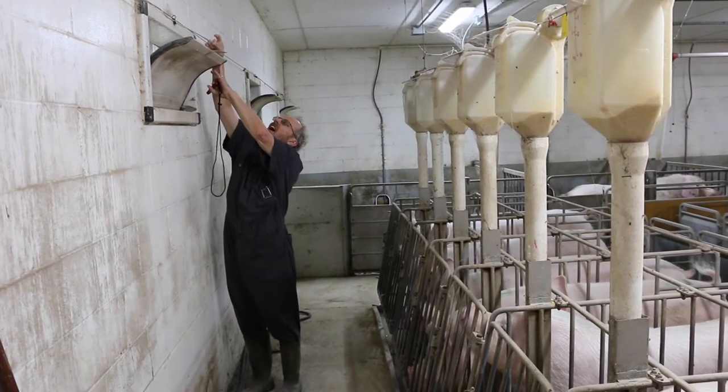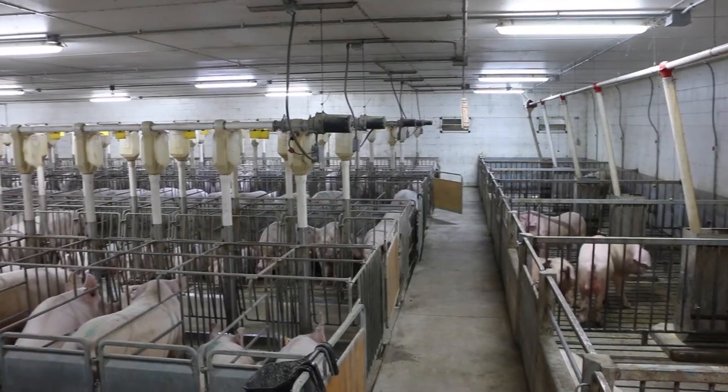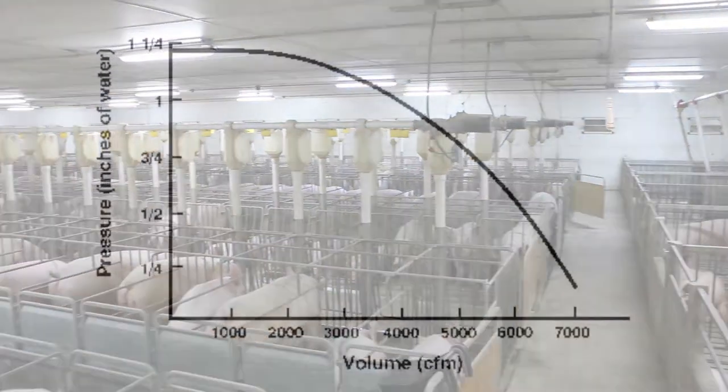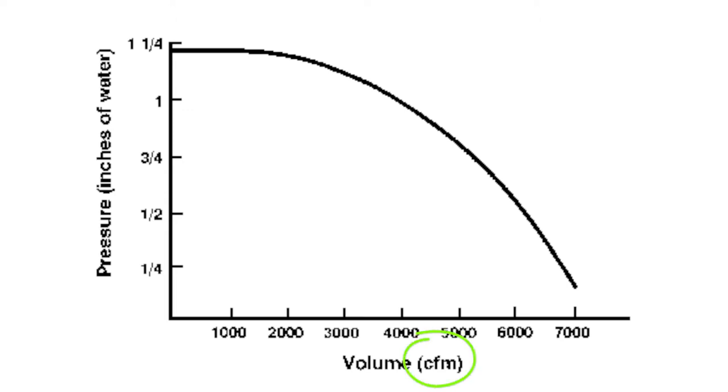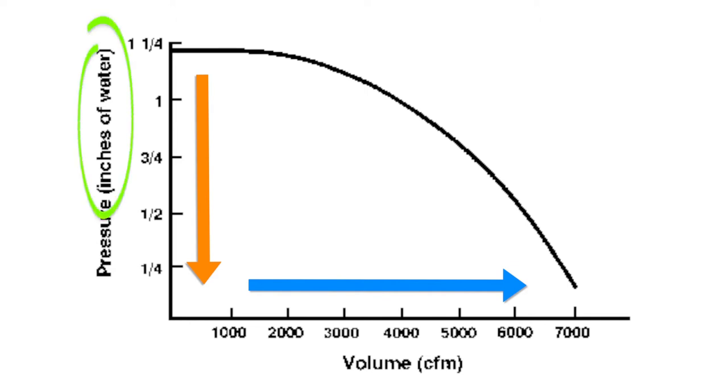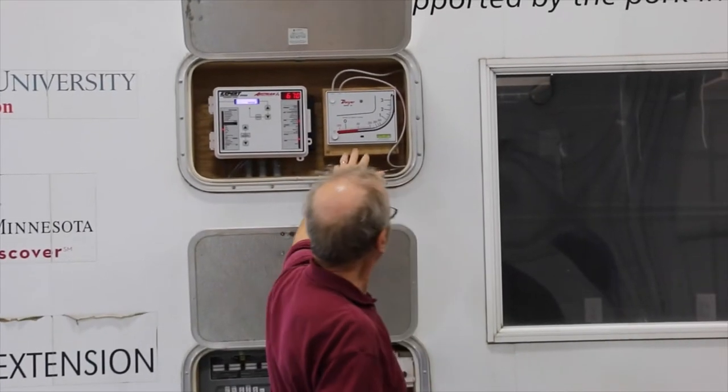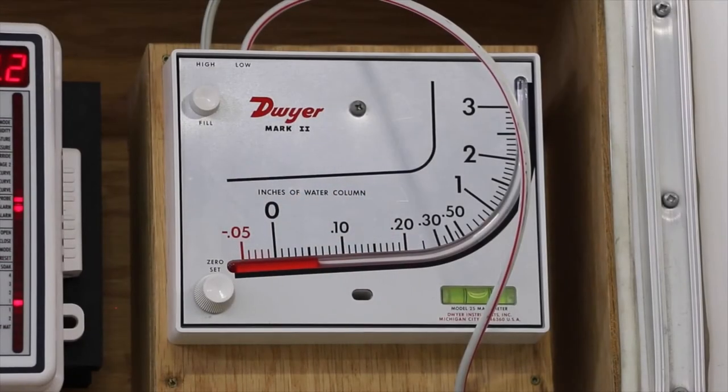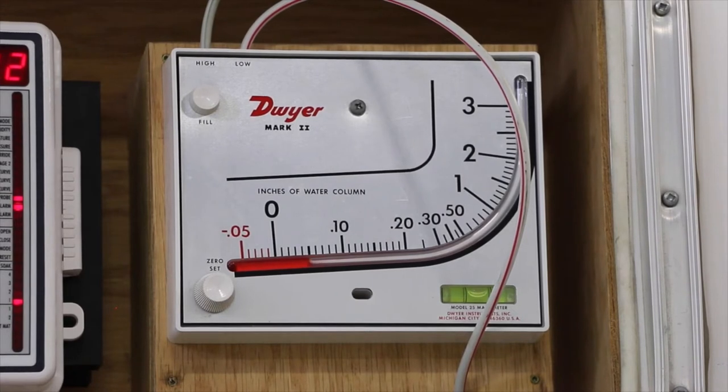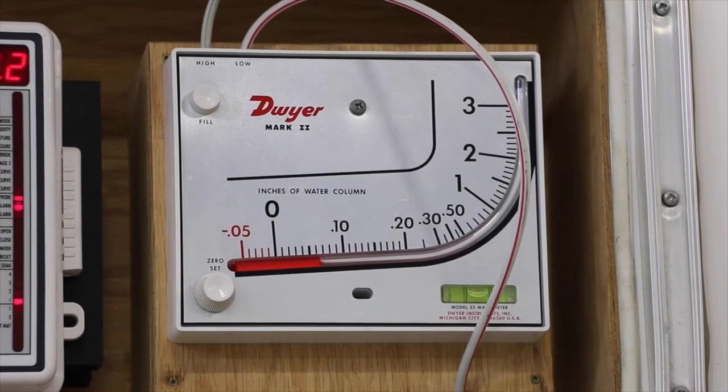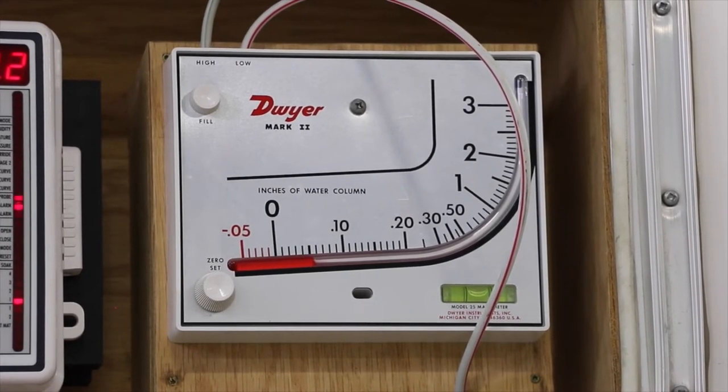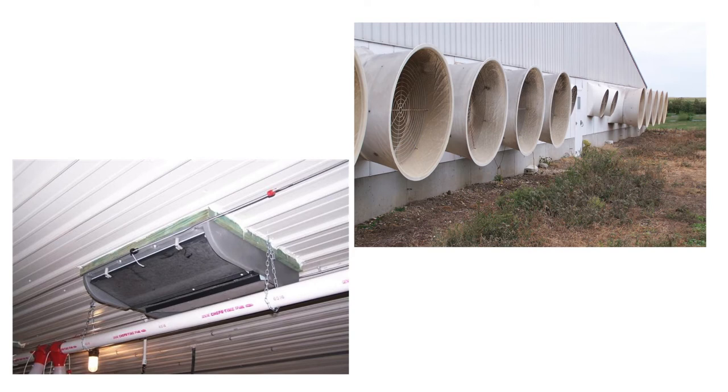Opening the inlet allows more air flow into the building, and the static pressure decreases. This graph shows how air flow, measured in cubic feet per minute, increases with decreases in the amount of static pressure, which is measured in inches of water. This is a device called the manometer that measures static pressure. Inside animal barns, the ideal static pressure should be between five hundredths of an inch and one-tenth of an inch in order to maintain good air flow. The fans and the inlets must operate together to maintain this ideal static pressure.